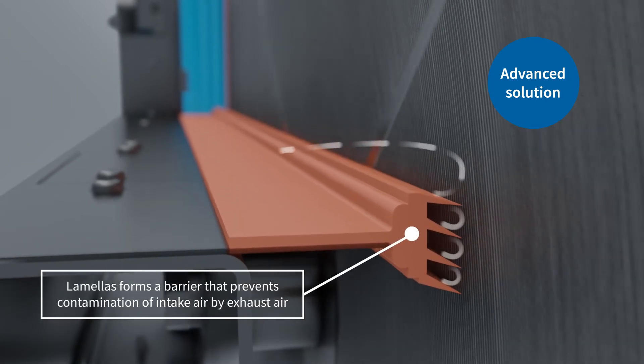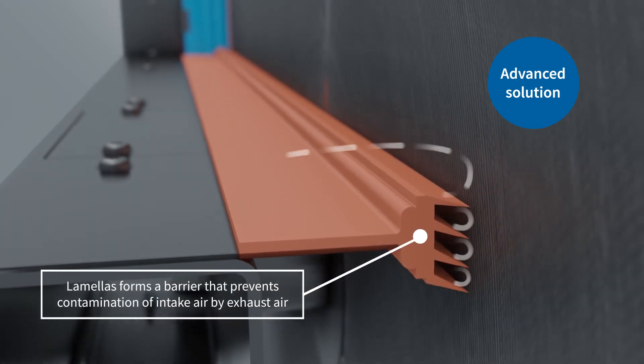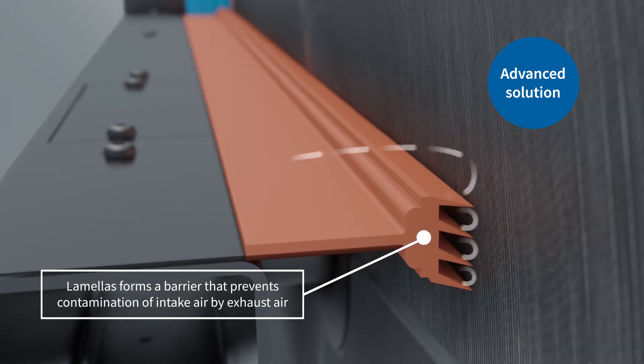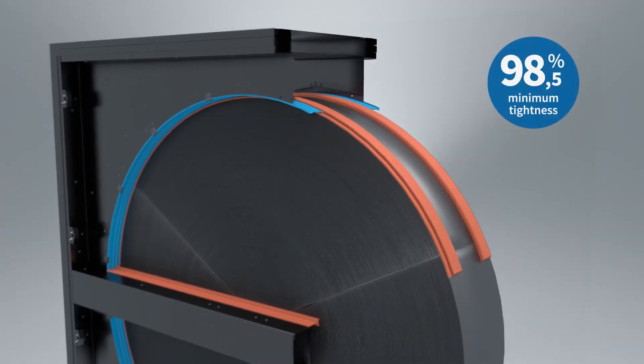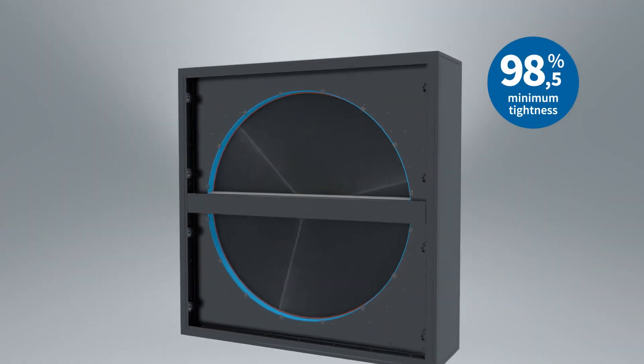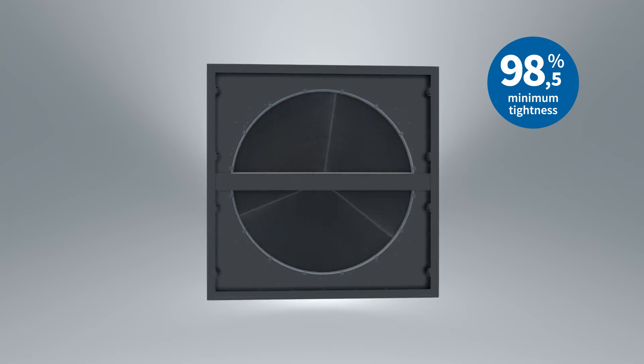This solution considerably reduces the overall untightness of the rotor, up to 1.5% of air volume at maximum. While designing air handling units, the need for energy to cover these losses is therefore considerably lower.